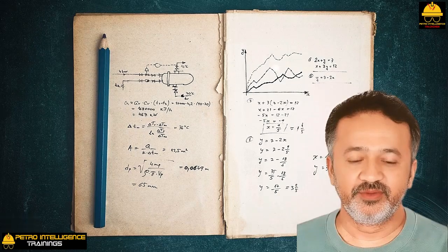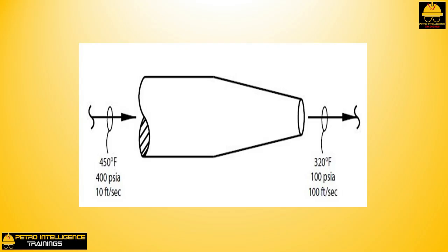Converting latent heat to velocity: Reducing steam pressure from 400 psi down to 100 psi in an isentropic manner as shown in the picture will have two positive results: high velocity steam at 100 feet per second that can do work, and 100 psi steam that I can use to reboil distillation columns.